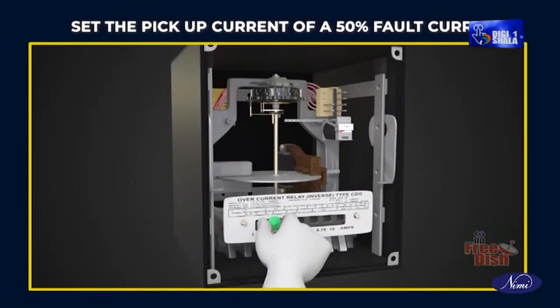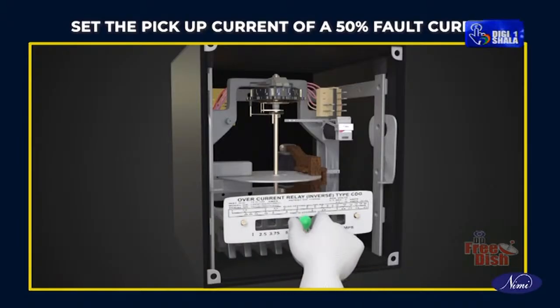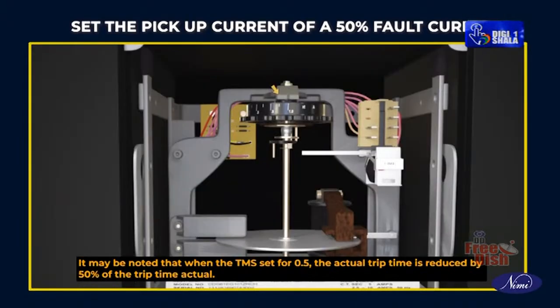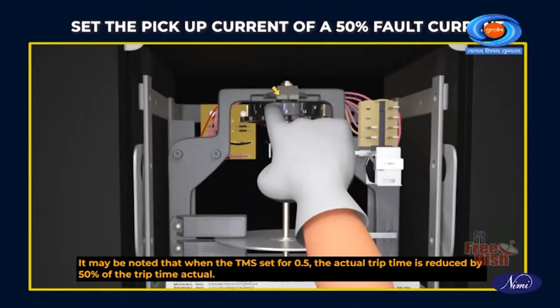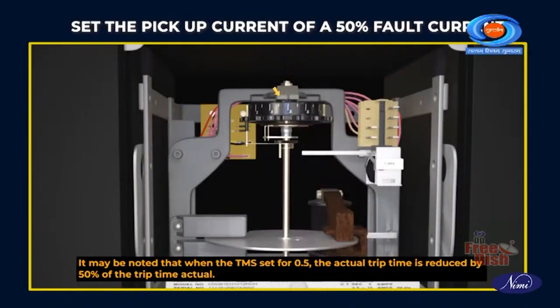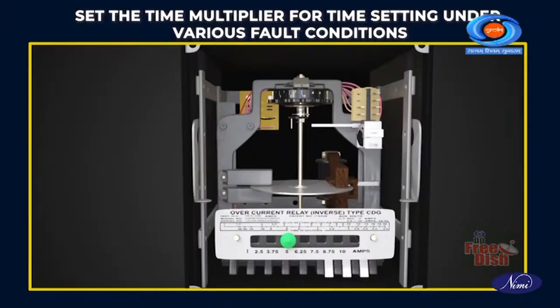Set the pickup current of a 50% fault current. It may be noted that when the TMS is set to 0.5, the actual trip time is reduced by 50% of the actual trip time. Set the time multiplier for time setting under various fault conditions.